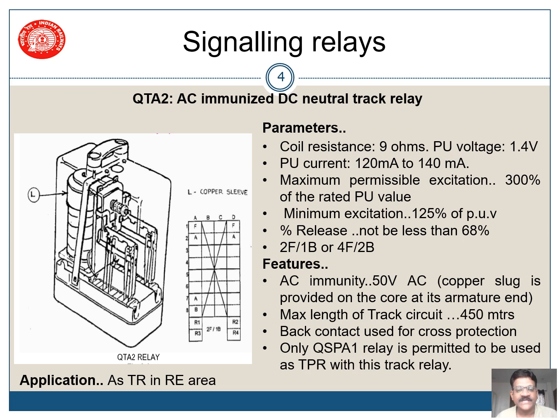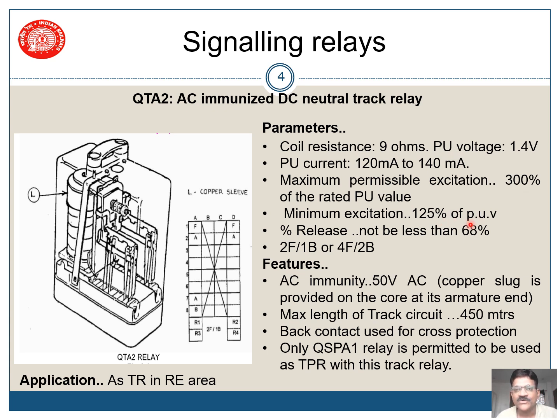Next we have the QTA2 relay. This relay is an AC immunized DC neutral track relay. Its basic parameters: coil resistance is 9 ohms, pickup voltage is 1.4 volts, and current rating is between 120 milliamps to 140 milliamps depending upon various factors. Maximum permissible excitation is 300 percent of rated pickup value, which gives up to 4.2 volts. Minimum excitation is 125 percent of rated pickup value, which comes to 1.75 volts. So the relay voltage should be between 1.75 to 4.2 volts for correct and proper operation. The drop-away percentage shall not be less than 68 percent.